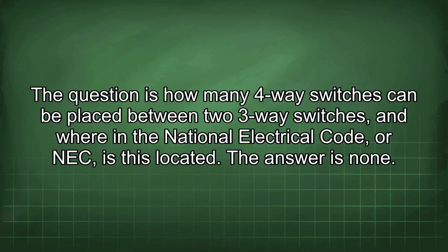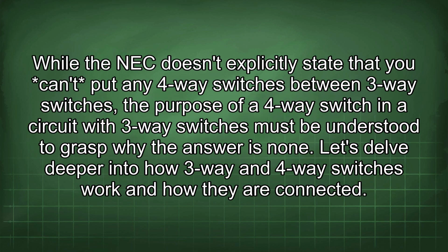The question is how many four-way switches can be placed between two three-way switches, and where in the National Electrical Code, or NEC, is this located? The answer is none.